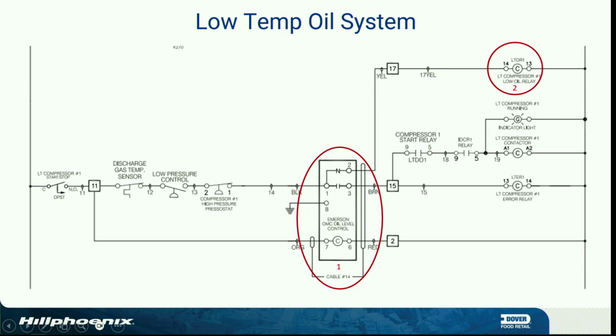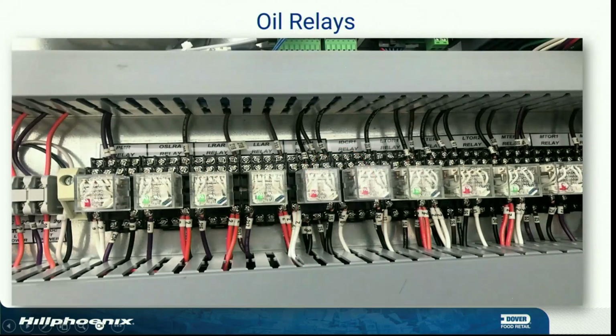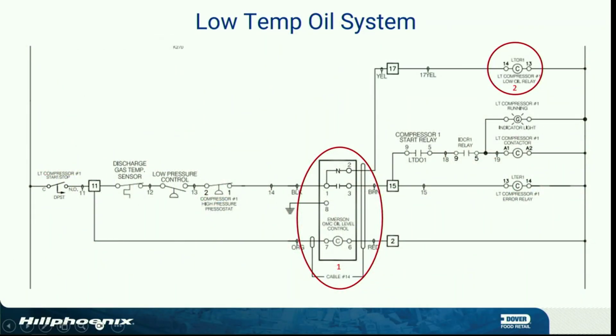All right, so our switch energizes. After 2 minutes of calling for and not filling, then we're going to energize our LTOR1 relay, which is our oil trip relay. Say we've got an oil trip. Or today on some of our new ones, you'll get a proof fail. Same thing. Because we actually wire our oil switches through our safety circuit. And our safety circuit has to be closed at all times for a controller to bring it on. If it's open, you're not going to get that compressor to cycle.